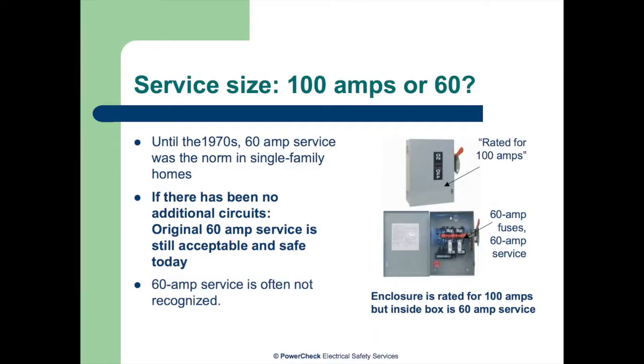Is your house 100 amp or 60? About 50% of the boxes will be pull switches. The other 50% will have a circuit breaker switch. But in the 50% with boxes, on every box it says rated for 100 amps. So people are saying I've got 100 amp service. Well, it's 60 amp in 99% of those boxes, if you open it up. The 100 amps is referring to the rating of the enclosure. So please open up the box and see what the fuses are. That's what determines the service size.